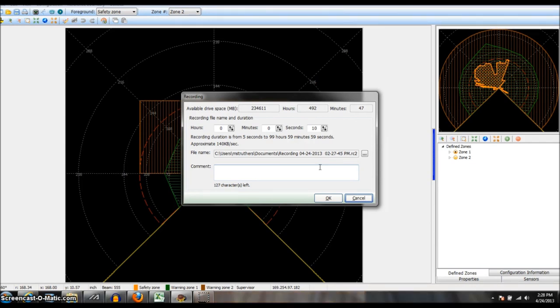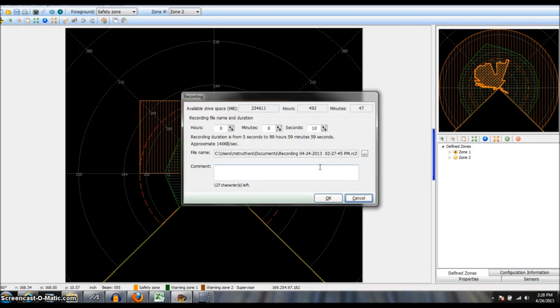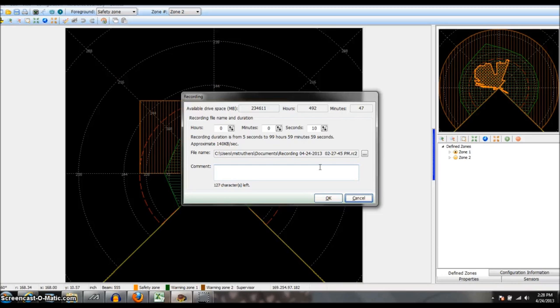For example if we have a dual zone guarding robot area we're free to be on say the left side of the room while the robot is doing its process on the right hand side. And then we exit the room and hit a button. The robot will move to the left hand side of the room. We are now free to be on the right hand side of the room. These inputs can be configured to switch between these two zones.